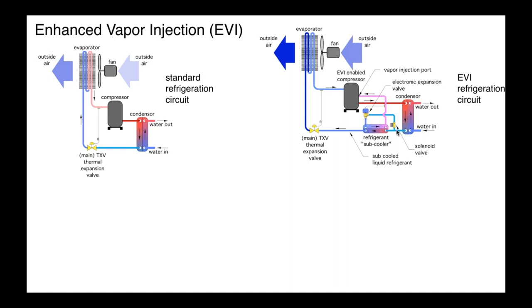So how are we going to do that? Well, we're going to send some of the liquid through the lower side of that heat exchanger, but we're going to open this solenoid valve and we're going to send the other portion of the liquid refrigerant into an expansion device, an electronic expansion valve. That's going to lower the pressure down and that's going to cause a cooling effect. When we lower the pressure, we lower the temperature. So we're getting a cooling effect. We're getting, in effect, another evaporation of refrigerant. So what is leaving out here on this pink line is a gas, but it is not at the low inlet suction pressure of the compressor. It's at an intermediate pressure. So what do we do with that gas?